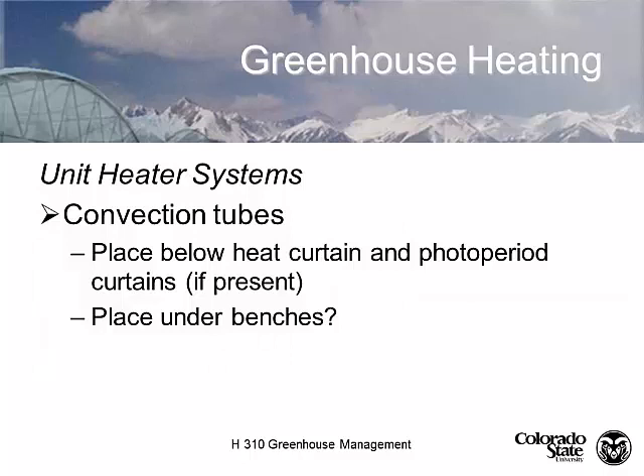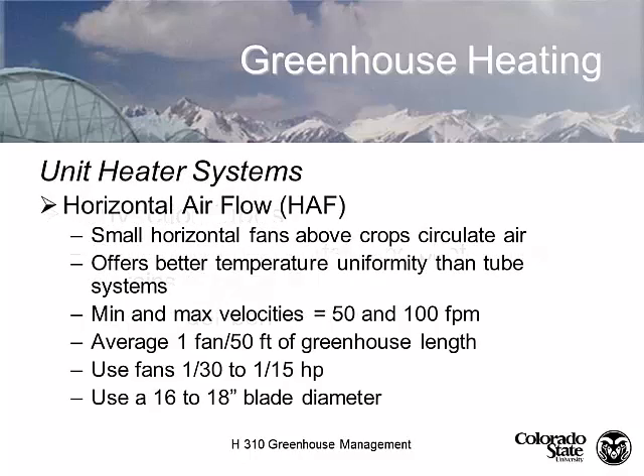You can also use convection tubes for under-bench heating — mount unit heaters low to the ground and run the convection tube under the benches to get air movement and heat rising. For most greenhouse air distribution, the modern choice is what's called a horizontal airflow fan — HAF fans. It's H-A-F, not half. A horizontal fan used to circulate temperature and give more uniformity.